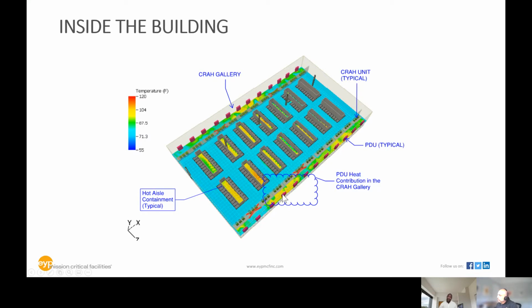Through that transformation of power, stepping it down or up, there are power heat losses. As you can see at the bottom where we have that cloud, that's the contribution of heat from the PDU into the gallery. So the cooling units in this case are sized not only to meet the cooling needs of the IT equipment, but also the extra heat rejected by the PDUs into the CRAH gallery -- they share that load together. This concept is what we usually call the flooded room or flooded cold aisle concept.